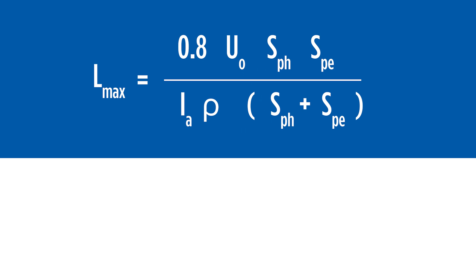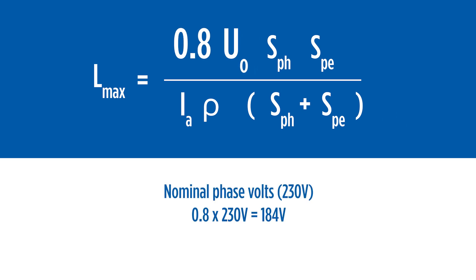When an installation's external impedance is unknown, it can be assumed that at least 80% of the phase voltage will be available at the protection device during a fault situation. In most cases, the external circuit's impedance will be low enough to allow for higher voltage values at the protection device. However, using the 80% voltage value will ensure calculated maximum lengths are always safe.